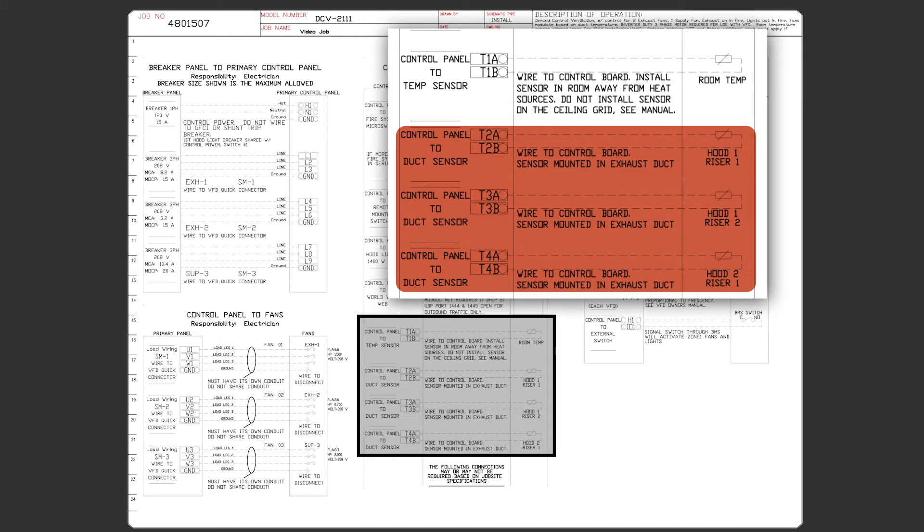The labels on each hood will give you the hood number and the riser. On the left of the hood when facing the hood is always riser 1 and riser 2 is always on the right. Just match the correct sensor to the wiring diagram and to the correct T terminals and terminate.